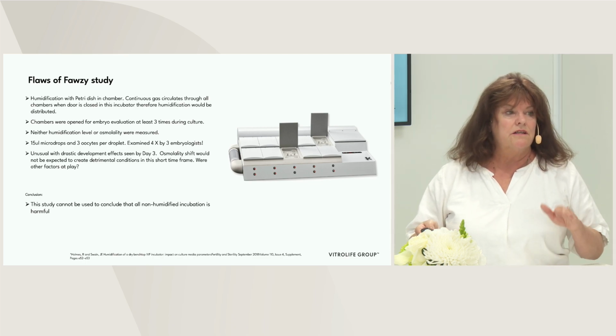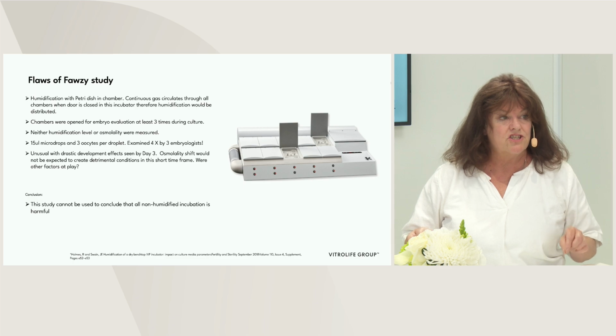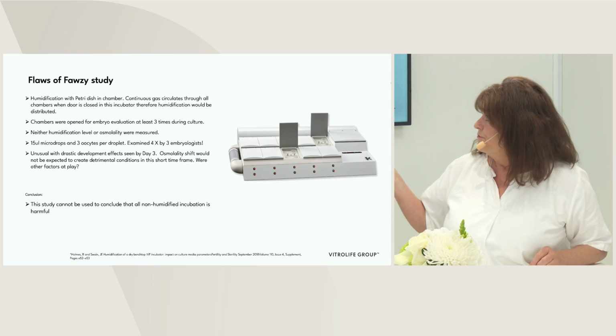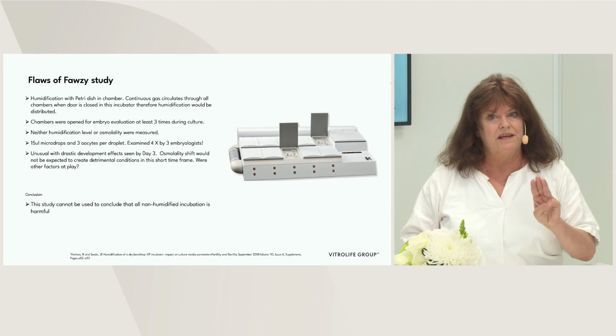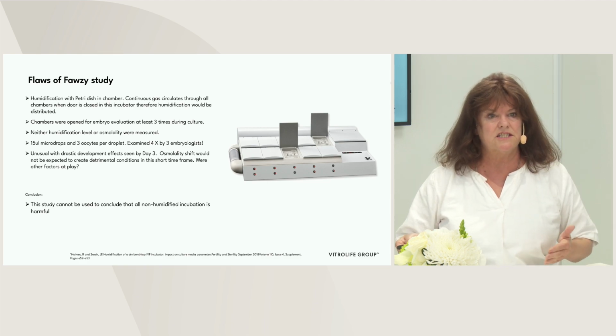Neither humidification levels nor osmolality were actually shown at all in these. Furthermore, it was a small microdroplet, 15 microliters with 3 embryos in it. So this would exacerbate the effect, particularly if you're looking at these systems. So this study cannot really conclude that all non-humidified incubation is detrimental by any stretch. However, it is the most cited.